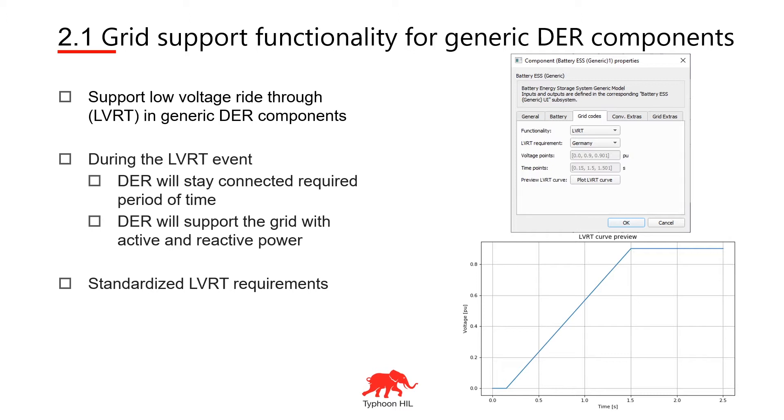DER will support the grid with active and reactive power during low voltage on the terminals. Also the LVRT functionality can be defined by standardized LVRT requirements or custom requirements.